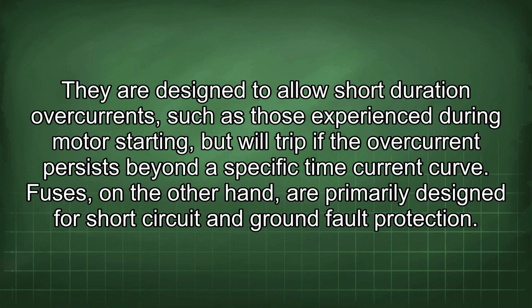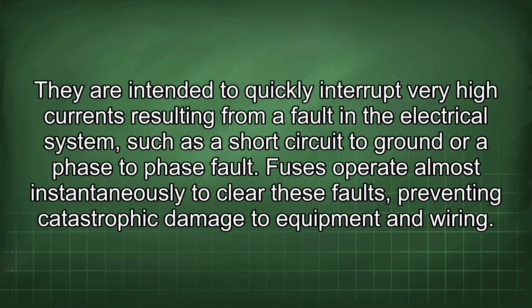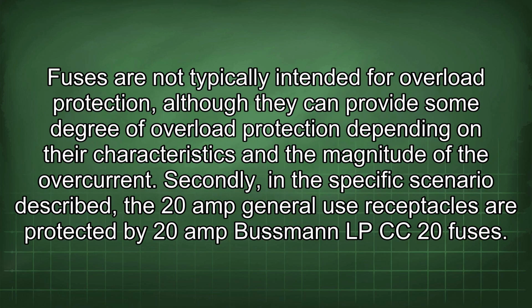Fuses, on the other hand, are primarily designed for short circuit and ground fault protection. They are intended to quickly interrupt very high currents resulting from a fault in the electrical system, such as a short circuit to ground or a phase-to-phase fault. Fuses operate almost instantaneously to clear these faults, preventing catastrophic damage to equipment and wiring. Fuses are not typically intended for overload protection, although they can provide some degree of overload protection depending on their characteristics and the magnitude of the overcurrent.